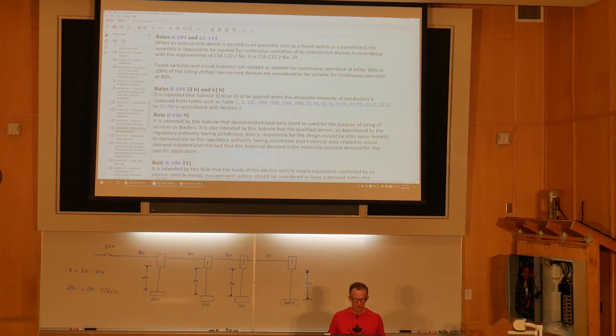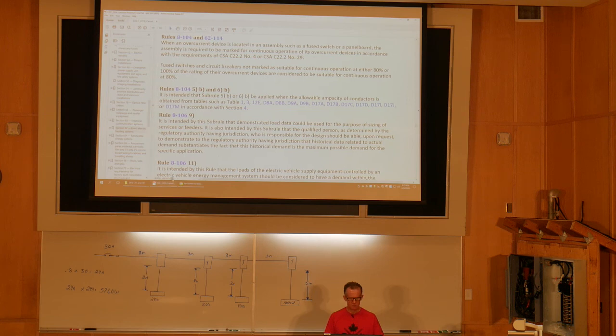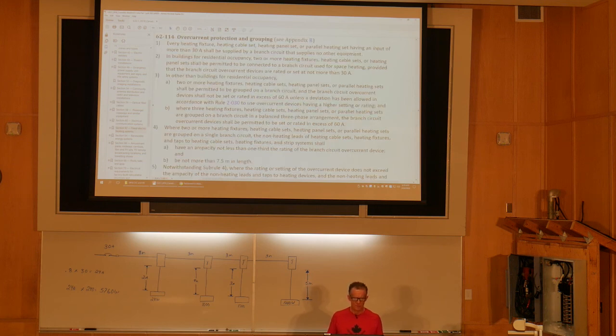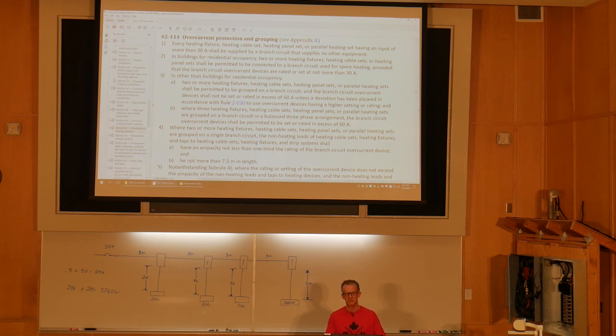What they're talking about here is 80% rated overcurrent devices, right? Heating, continuous load. Fuse switches and circuit breakers not marked as suitable for continuous operation at either 80% or 100% of the rating of their overcurrent devices are considered to be suitable for operation at 80%. So in a previous video on this rule, 8-104, we looked at continuous loading. It applies to heating. So that's what that note's about, and you'll see in the rules coming down as we go here.